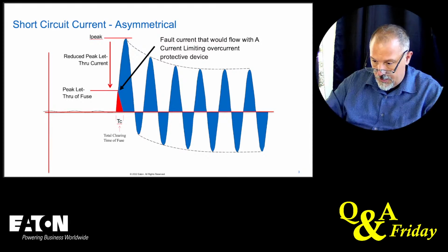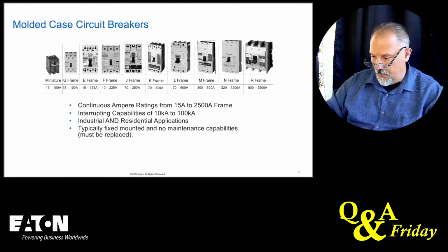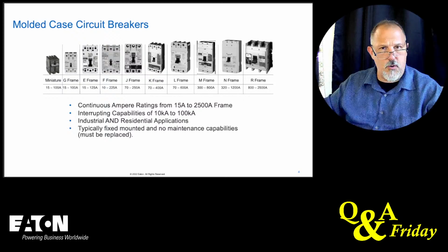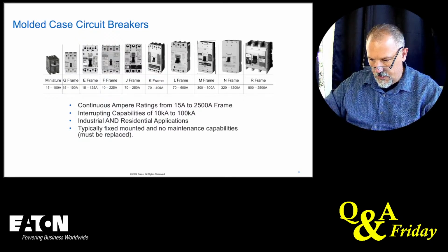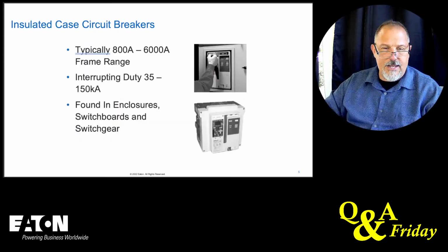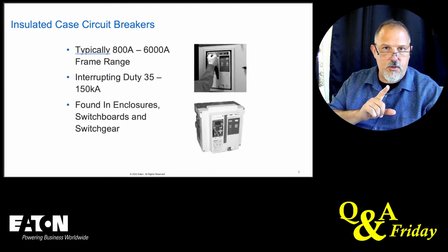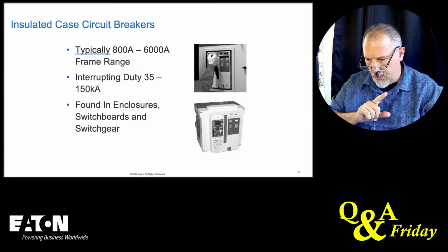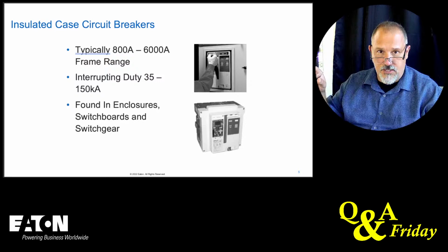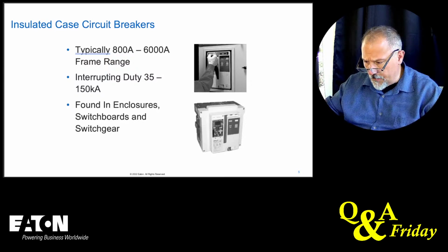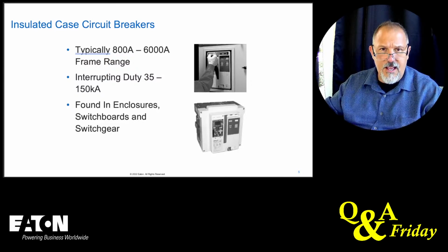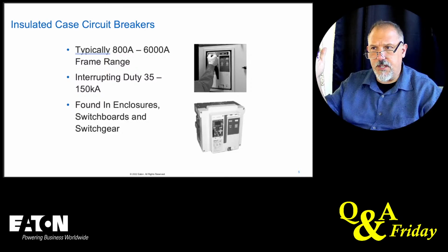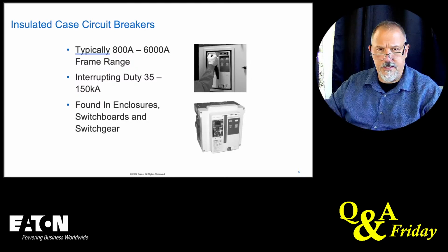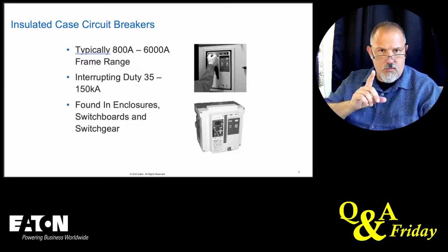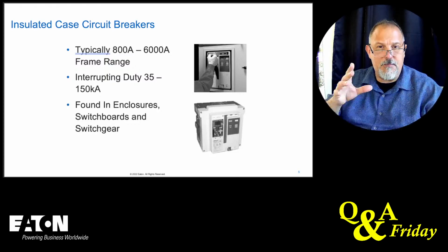Okay, so you take a look at molded case circuit breakers. A family of molded case circuit breakers, we go all the way up to 2,500 amps. Insulated case circuit breakers, it's still a UL 489 device. It goes up to 6,000 amps, interrupting ratings of up to 150,000 amps, and as low as 800 amps, in which you could get the long time pickup to be even lower than that. We're going to look at the trip curve a little bit later, but that beast is big.